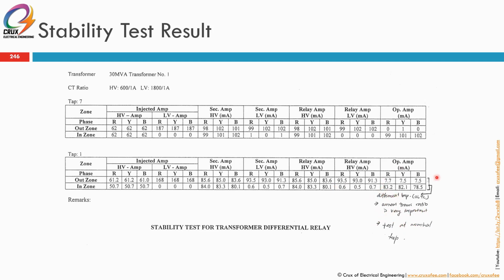Alright. So if you are testing at different tap for differential, you will get a little bit different result. This is due to the ratio of the transformer. So you have to calculate back based on the actual tap where the transformer is at that point of testing.